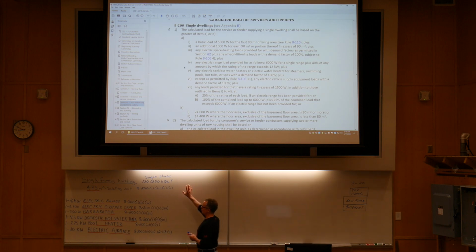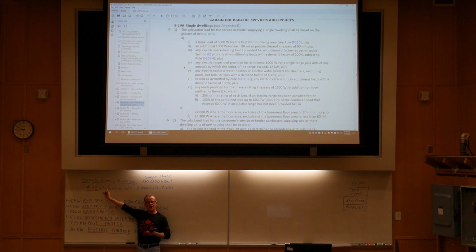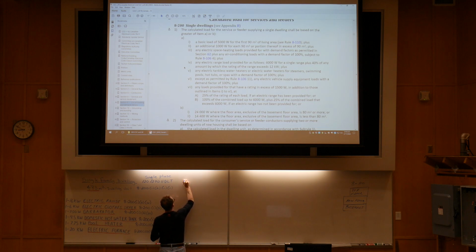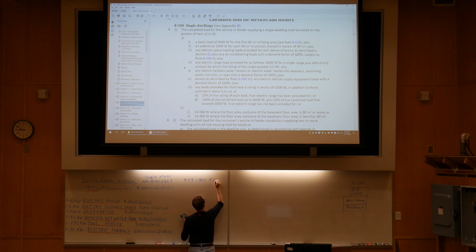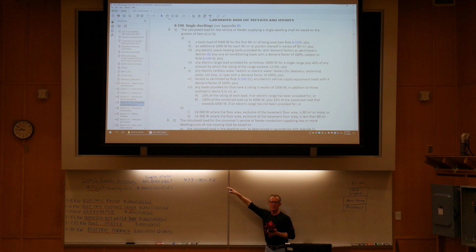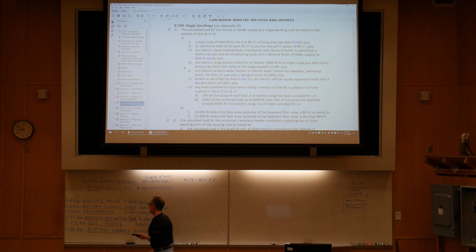Now I will perform the calculation on the board. You've got the rules here. All right? Here we go. First thing I do, I take the 473 and I subtract 90. And now, that is my portion. So the first 90 square meters goes in at 5,000 watts.